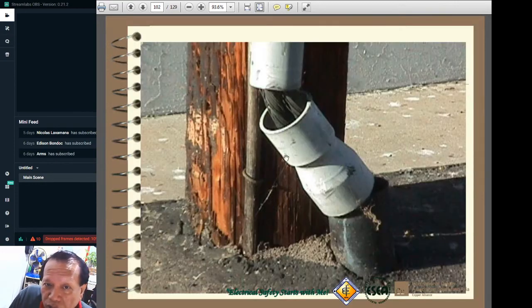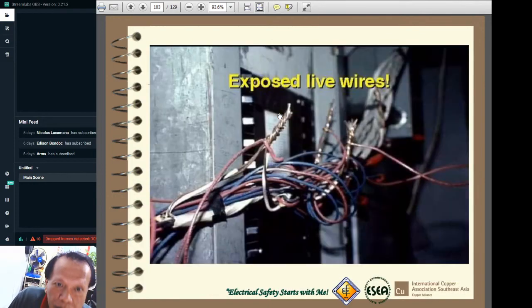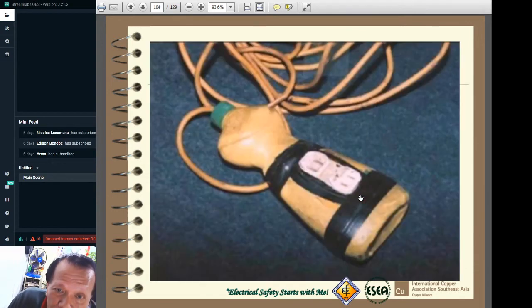Here is also a violation of the code because the installer just simply did not provide for a firm connection of the conduits. This is a coupling, so it's already been detached from the conduit and therefore exposing the cable or wire. There's also another one where splices are exposed, so very dangerous. They should be provided with electrical tape or splicing tape, to prevent possible short circuit or electrocution.